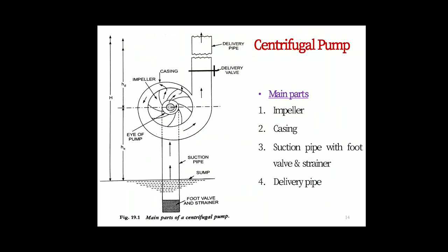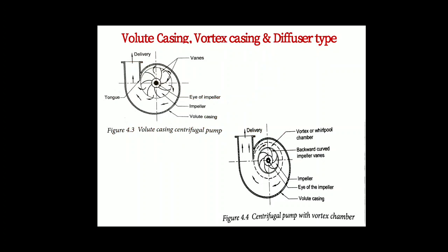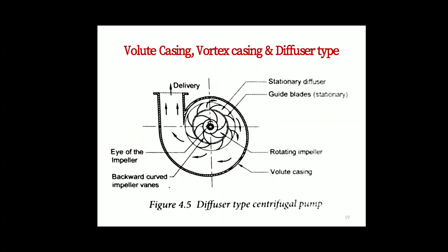After the rotating of this mass of liquid through this volute casing or spiral casing or vortex casing, the pressure rise will be built up and the pressure increases. This high pressure water will be given to the required height or elevation. This is how a centrifugal pump works. The main purpose of this casing is to increase the pressure. The design is such that the area of cross-section is gradually increasing from point to point.